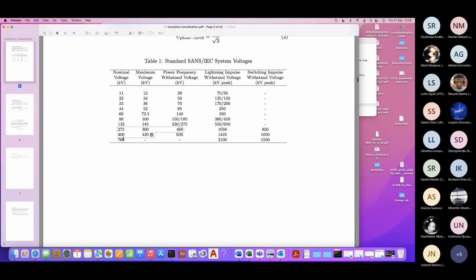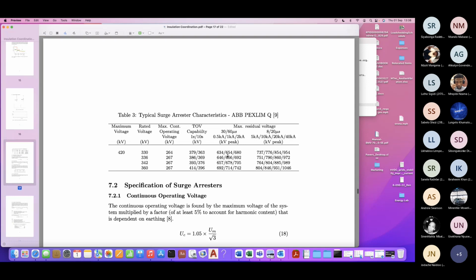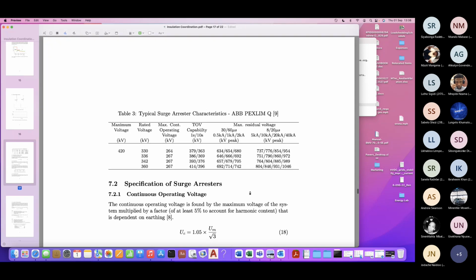Right. So if we look at this table, that was for a 400 kV system, that surge arrestor gives a power frequency withstand of 630. Lightning impulse withstand is 1425. If we look at all of those ratings here, they're all below 1425. So our equipment will have a BIL, and our surge arrestor will usually bring our voltage within the limits of that BIL by conducting the current away.